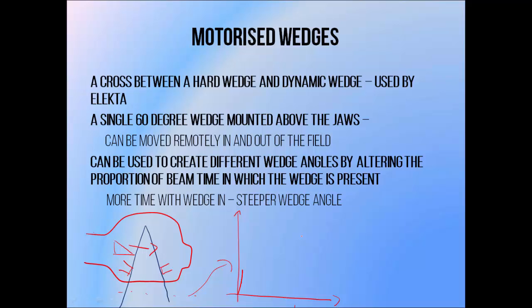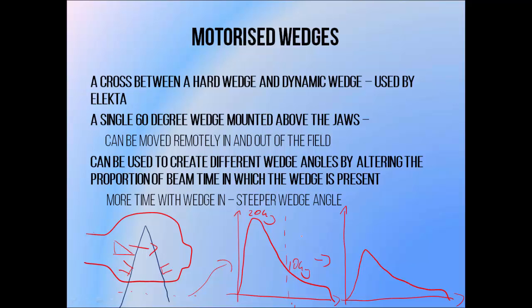Say we want to deliver 10 grey to the centre of the beam. If we want to use a 60-degree wedge angle, we deliver the entire field with the wedge in place, winding up with a much higher dose on one side — let's say 20 grey, twice as much as in the beam centre. If we want a shallower wedge angle, we can deliver part of the beam with the wedge in place and the remainder without. Delivering 5 of the 10 grey to the centre using a wedge field, then another 5 grey with the wedge out, gives 10 grey in the centre but only 15 grey on the high side instead of 20 grey. So the ratio of the highest dose to the centre dose drops from 2:1 to 3:2. We can therefore adjust the wedge angle by adjusting the ratio of beam delivered with the wedge in versus out.